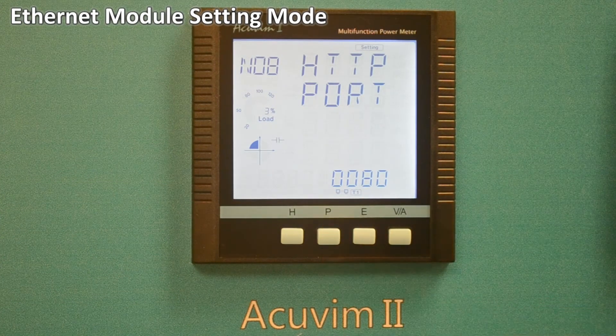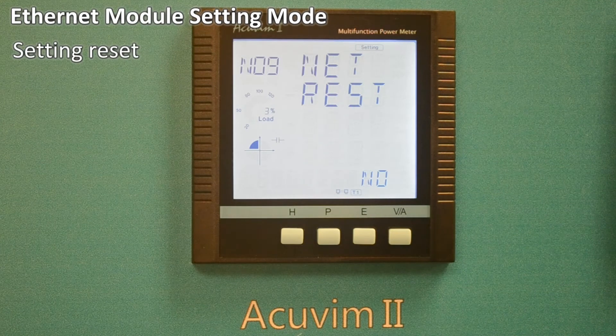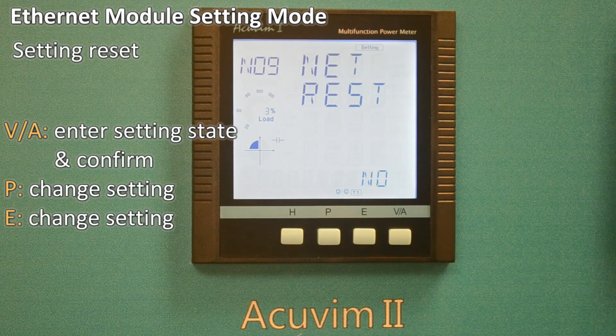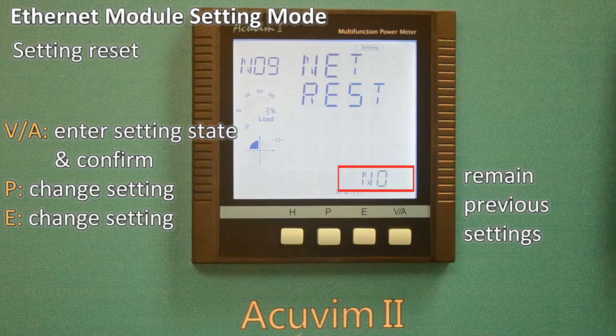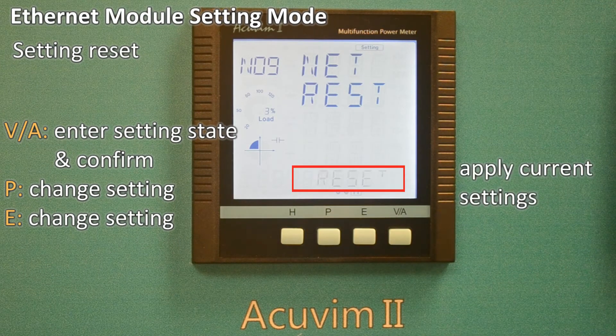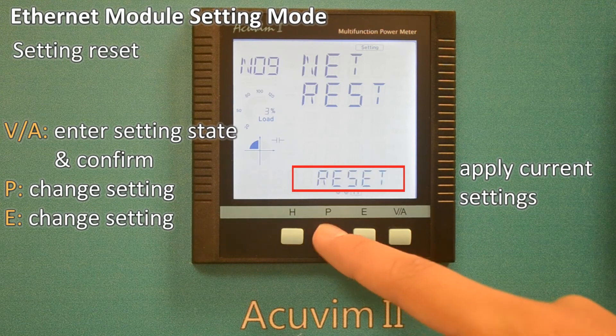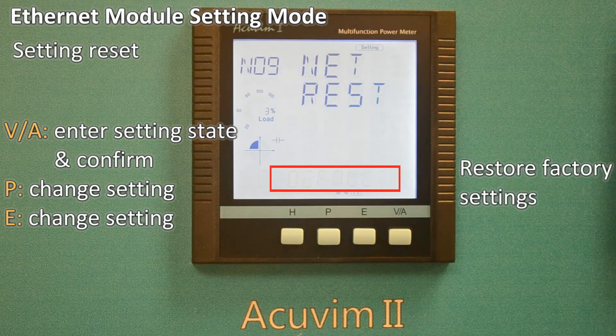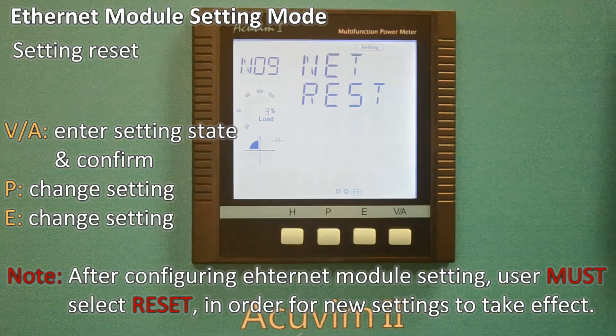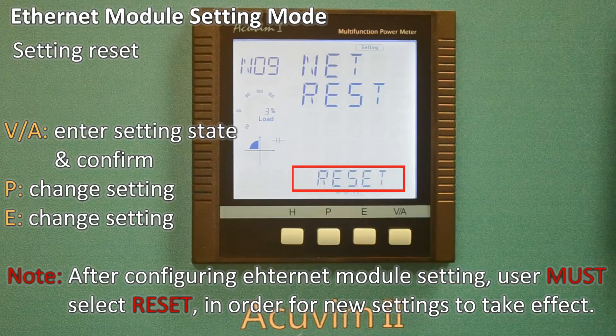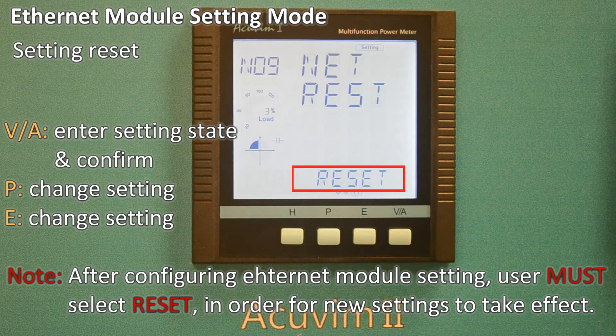The settings can be reset in this screen as well. To reset, press VA to enter the setting state, and press the P key to select configuration mode. By selecting No, the module settings will remain. Selecting Reset will reset the module setting. Selecting Default will load the module with default settings and reset the module. Please note: after configuring the Ethernet module settings completely, the user must select Reset to restart the module. This is necessary for the new settings to take effect.